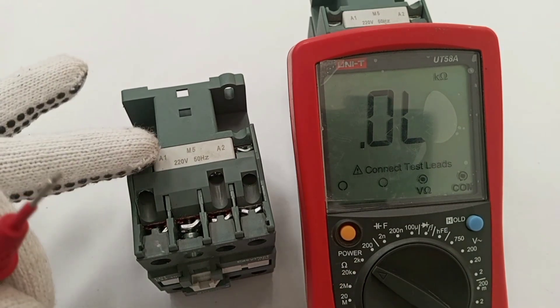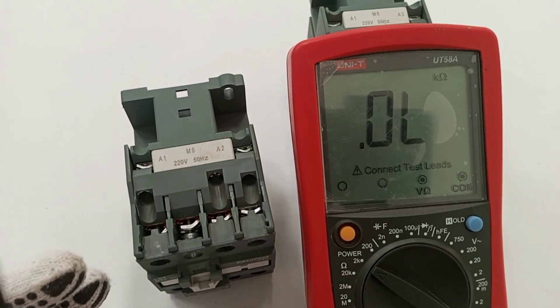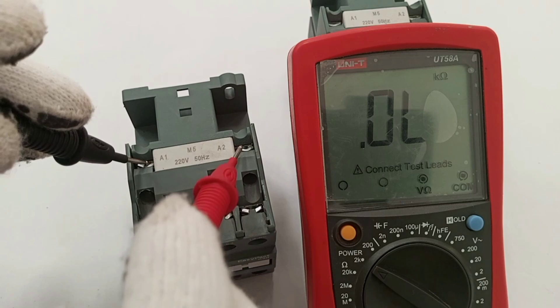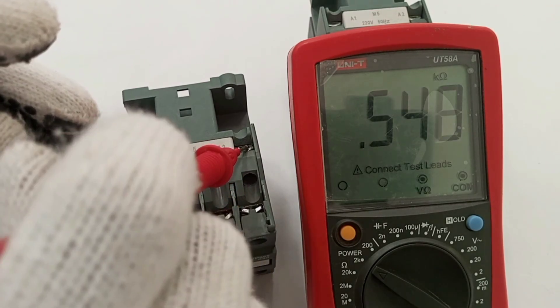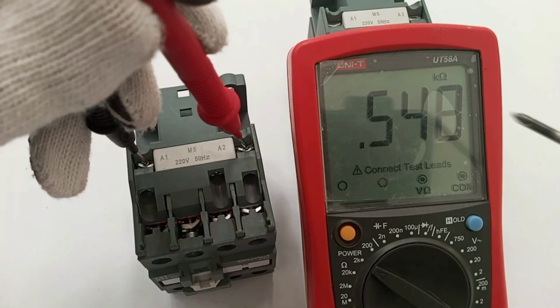We can also test at the 2 kilo-ohm range. At 2 kilo-ohms, if there is a short circuit in the coil the meter should read zero or a very low resistance, but if I'm able to read a considerable amount of resistance then that tells me it is working. Here — A1 and A2 — and I have 0.548 kilo-ohms.